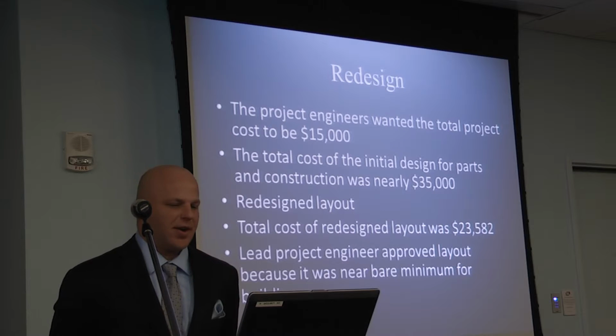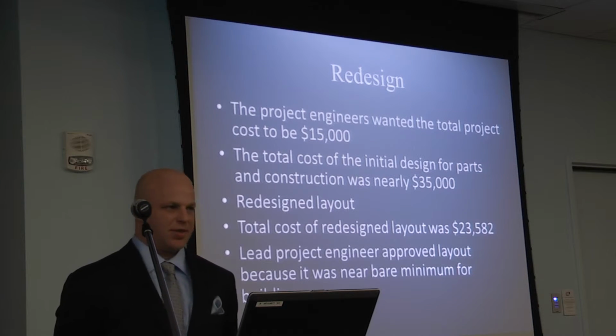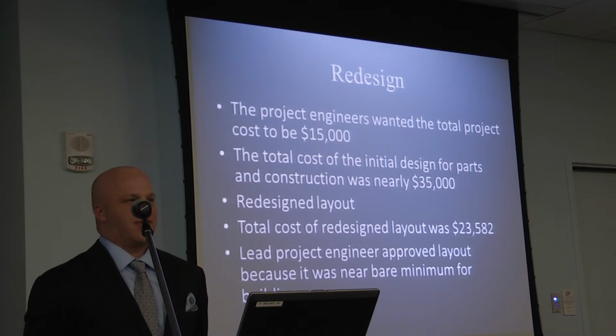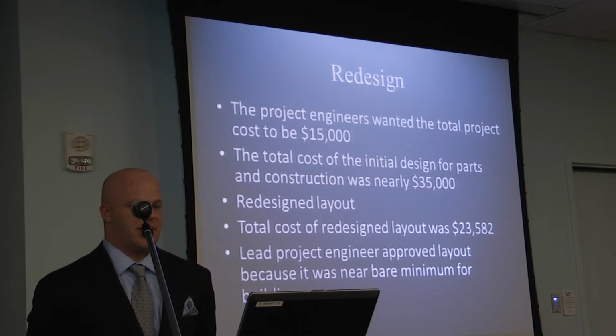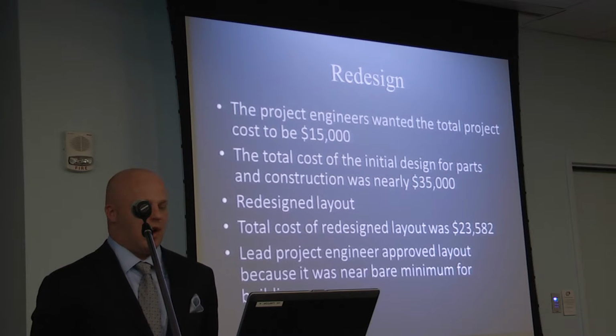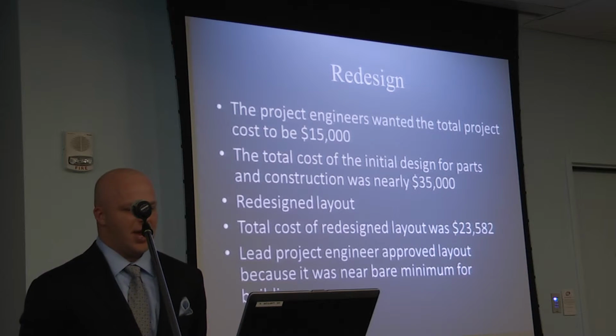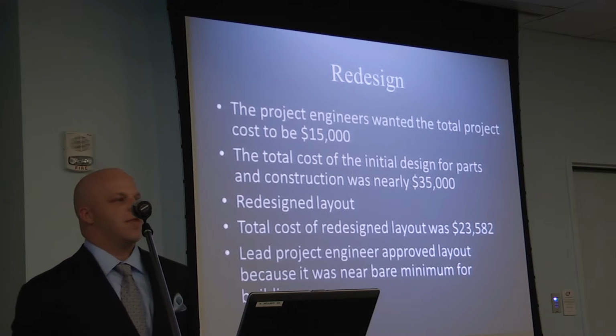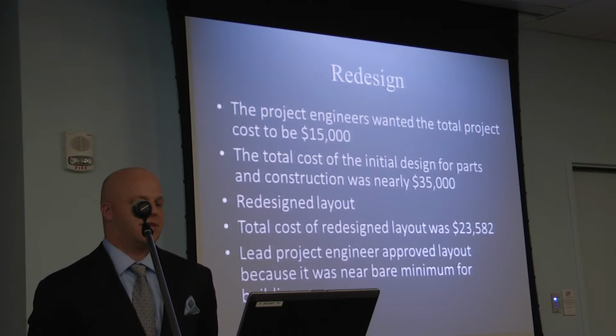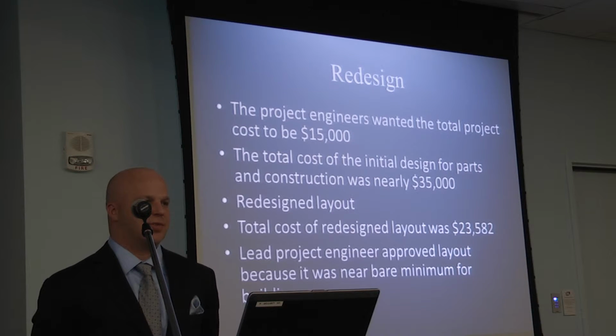A redesign was required after figuring up the total cost of the project. It was near $35,000, and the project engineers approached us and said that that was way too much. They were looking for something more like $15,000, and that was for the construction of the electrical equipment as well as the parts themselves. So I had to redesign the layout, and doing this, I removed all the fluorescent fixtures, which was suggested to me, because with the fluorescent fixtures mounted at 20 feet above the ground, it can be a pain to have to change the bulbs out, so I can certainly understand that.